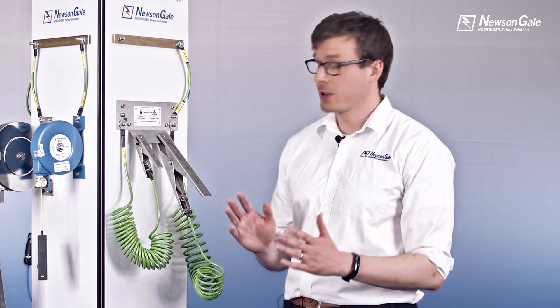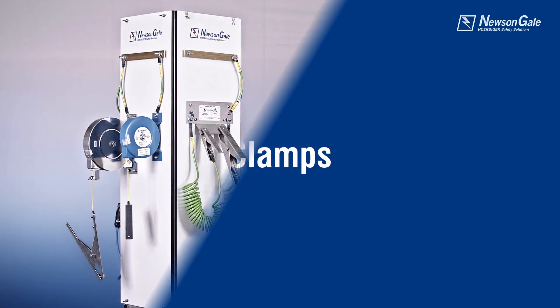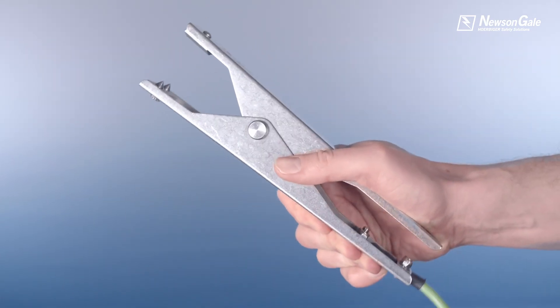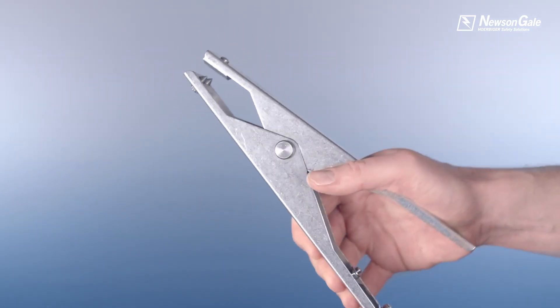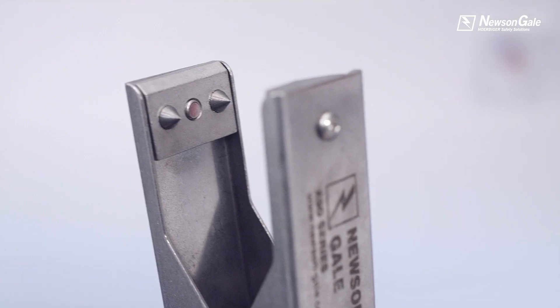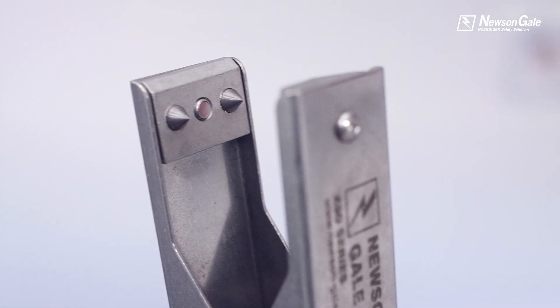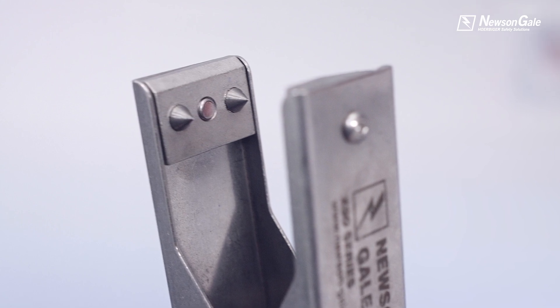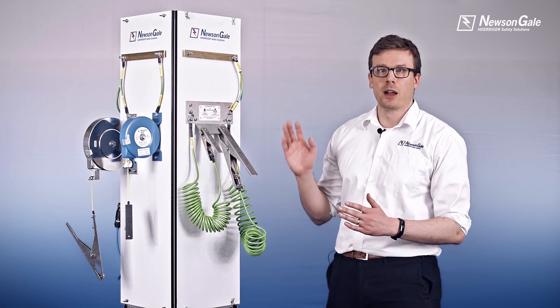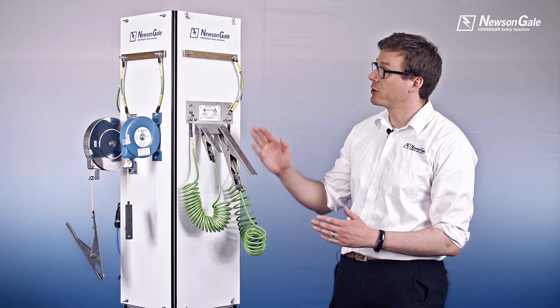Let's first look at the clamps. Our ergonomically designed clamps are manufactured from stainless steel with a torsion spring to provide strong clamping force to the teeth while providing good corrosion protection. The robust tungsten carbide teeth provide a sharp point to reliably and easily penetrate rust or layers of coatings down to the bare metal. This helps the operator achieve and maintain a low electrical resistance connection and a safe ground path for electrostatic charge dissipation.